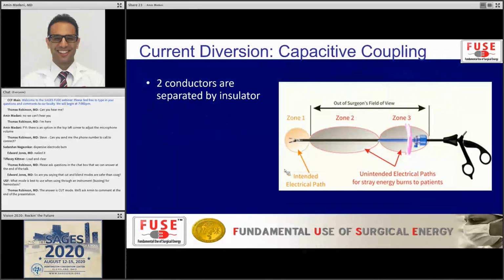Finally, the last thing here is capacitive coupling. It's like you have antennas that you're working with in the operating room. Just because this is covered by insulation, and let's assume for argument's sake there's truly no break in the insulation, and just because I'm looking at the field of view at the metal tip, it doesn't matter. Things can happen outside your field of view without you even knowing about it. Imagine there's another conductor beside it. You can actually communicate like antennas through insulation, through air, to that other conductor and induce a new current in that other conductor, causing a burn somewhere completely outside your field of view.